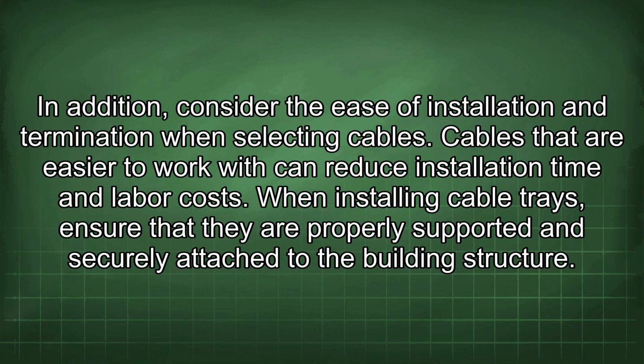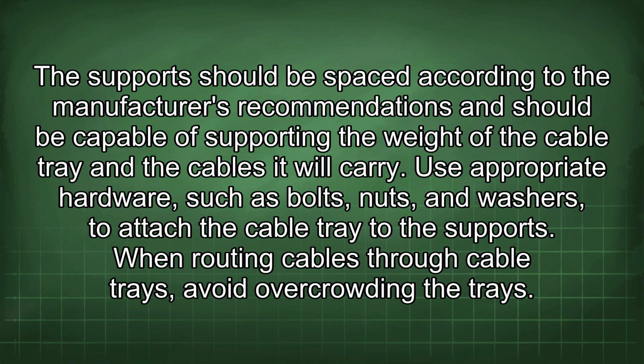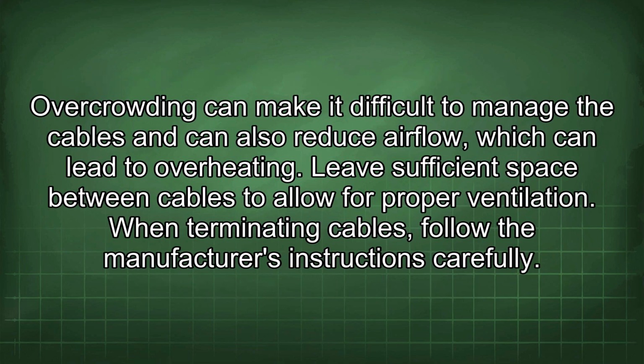When installing cable trays, ensure that they are properly supported and securely attached to the building structure. The support should be spaced according to the manufacturer's recommendations and should be capable of supporting the weight of the cable tray and the cables it will carry. Use appropriate hardware, such as bolts, nuts, and washers to attach the cable tray to the supports. When routing cables through cable trays, avoid overcrowding the trays. Overcrowding can make it difficult to manage the cables and can also reduce airflow, which can lead to overheating. Leave sufficient space between cables to allow for proper ventilation.